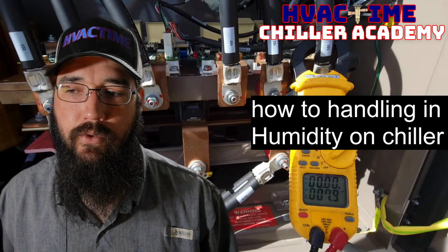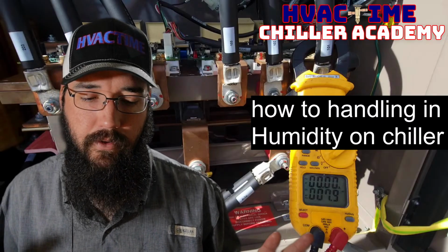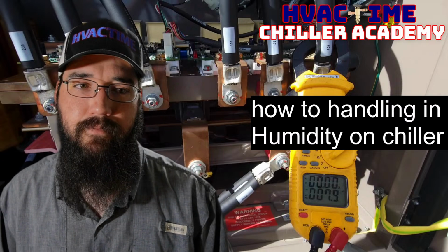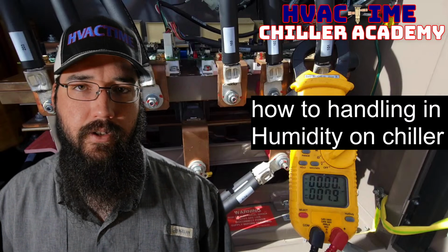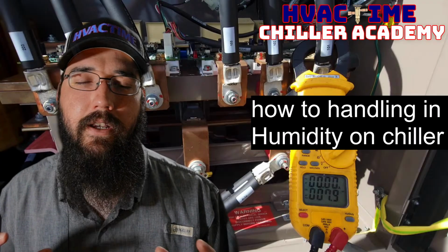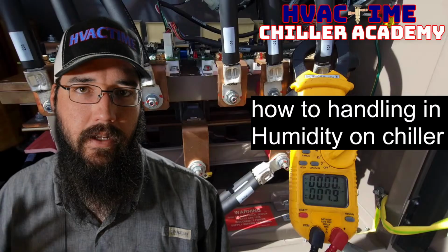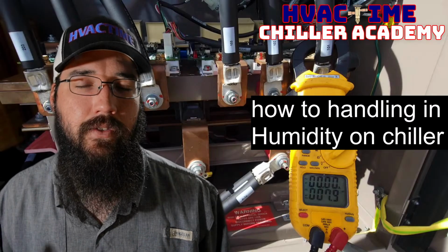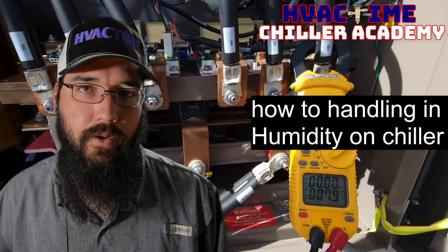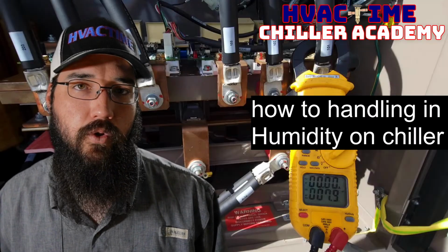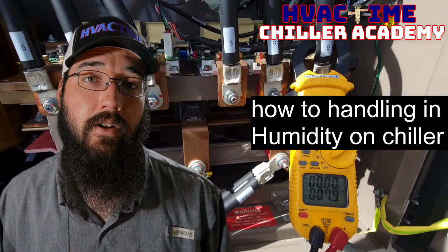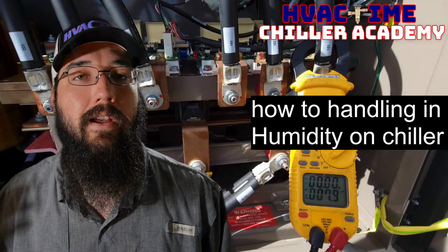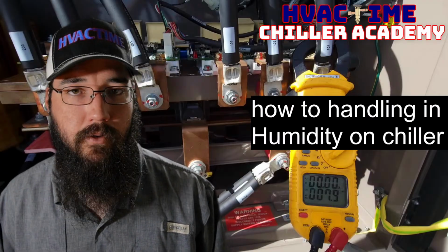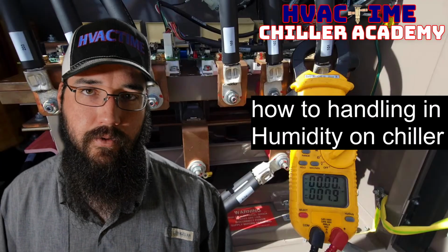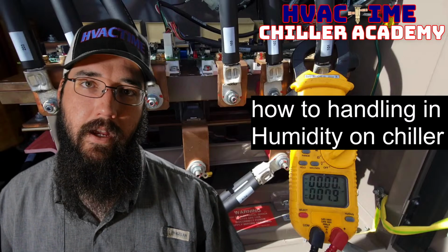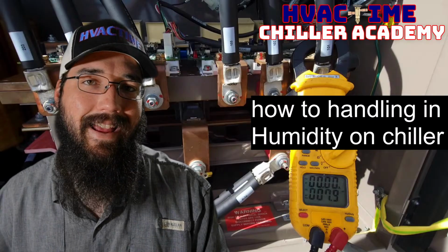And I do want to clarify, just in case this is not fully understood. In terms of humidity at the chiller itself, humidity will impact a water-cooled system if it has a cooling tower. So we're talking ambient outside humidity at this point, because a cooling tower's ability to control leaving water temperature out of the tower is based off of the wet bulb temperature. So the more humidity we have outside, the higher our wet bulb is going to be, the more our cooling tower is going to struggle. So you'll have to take that into account, and that's how humidity can affect a water-cooled system.